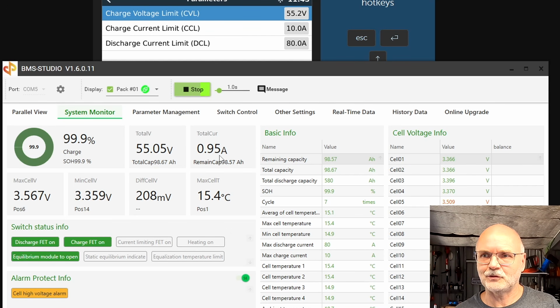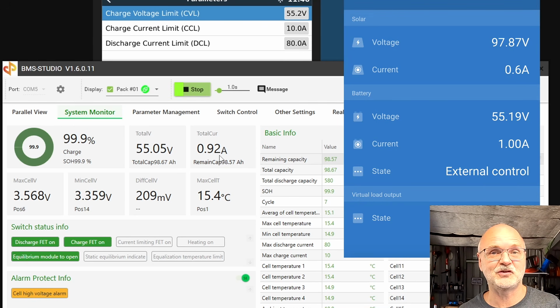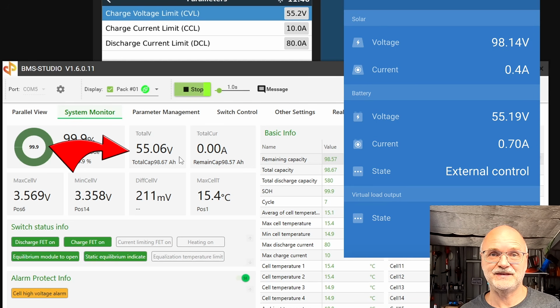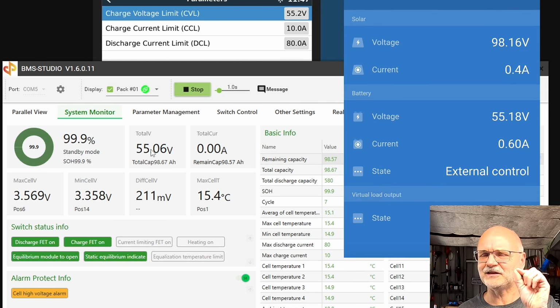Let's have a look at the solar charge controller. It's doing fine, it does exactly what it's told by the BMS, it charges to 55.2 volts. So our battery will never reach 55.2 volts, never ever, because the measurement of the BMS and the charger, the MPPT, are different. This is partly because of a voltage drop, since the MPPT is further away from the battery.